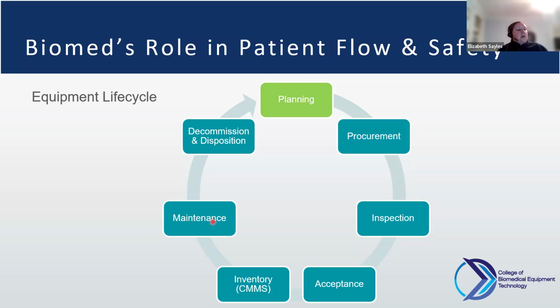So over time, as I mentioned, those infusion pumps are going to need maintenance. This is going to depend on the medical device manufacturer's recommendation for maintenance. It could also be based off of what your organization decides to do aside from manufacturer's recommendations, because in some instances, you can do what's called an alternative equipment maintenance plan, which means that you can do maintenance that's different from the medical device manufacturer. So you're going to end up doing maintenance over time on the different devices that you're going to see. If it's year one after the infusion pumps are purchased, you're going to be doing maintenance on those infusion pumps. You're going to be testing them, doing functional testing. Some infusion pumps you'll do electrical safety, not all. And you'll be rotating through and testing those over a time period.